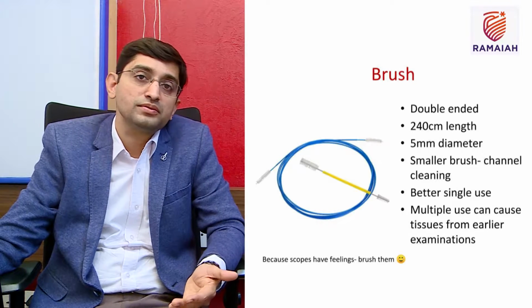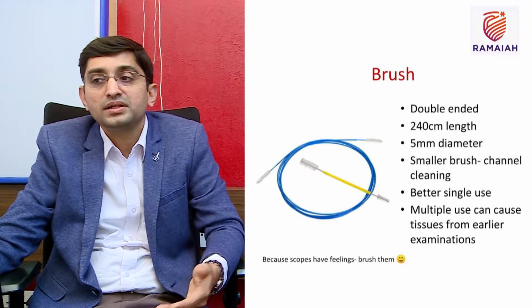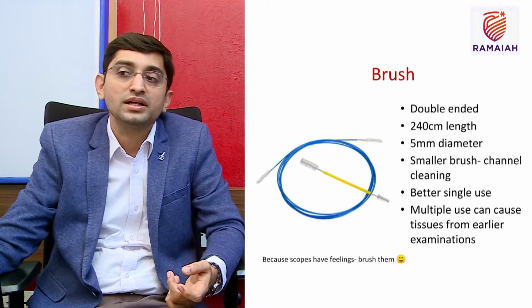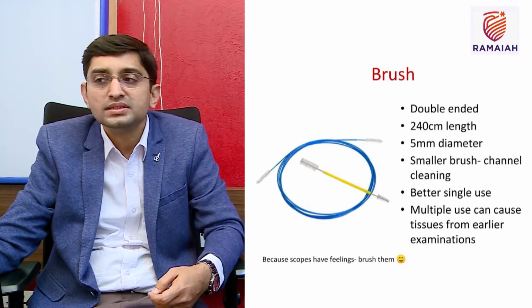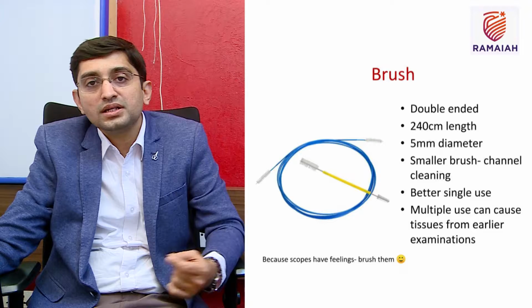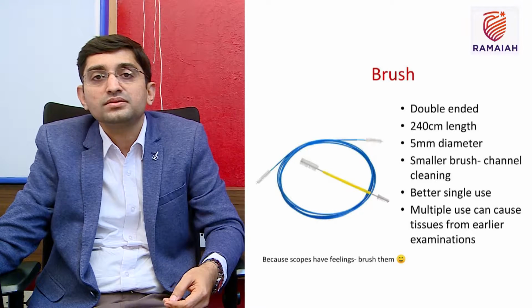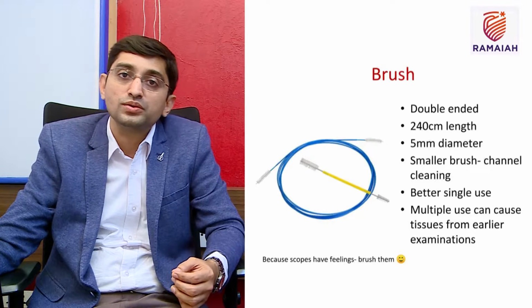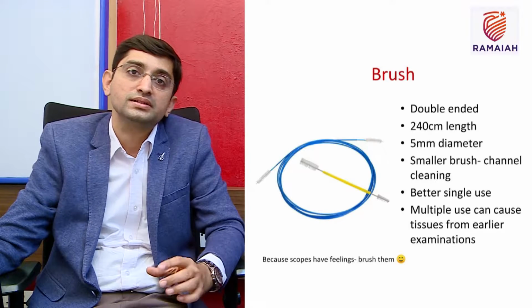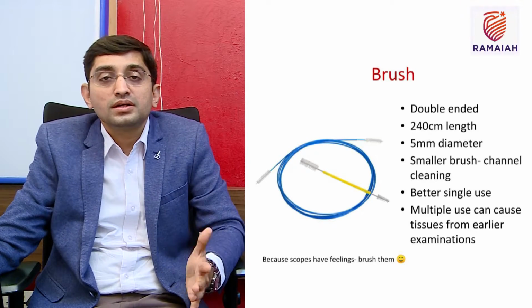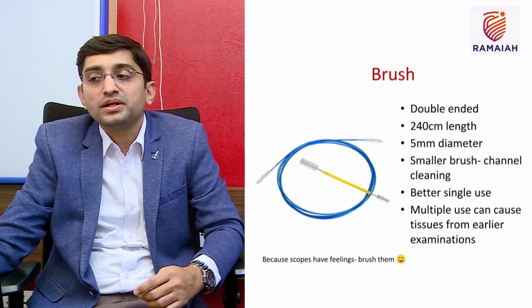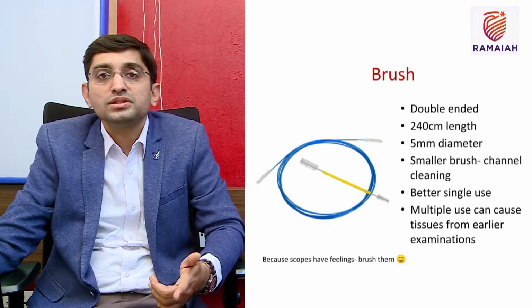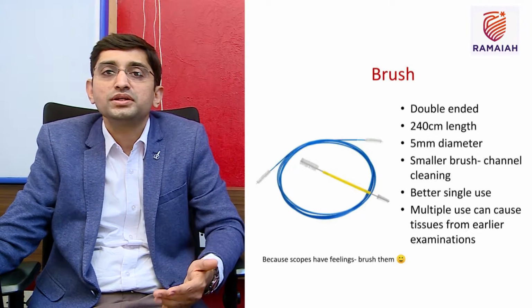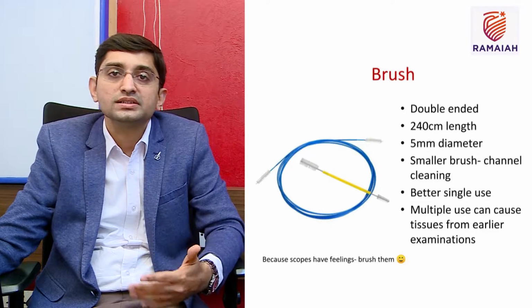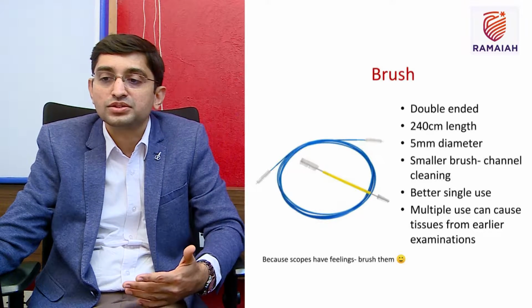You can use a scope cleaning brush, which comes in 2 different sizes. One is a longer tube, which is around 240 or 200 centimeter. The second one is a smaller tube, around 10 to 15 centimeter, with a brush at both ends. Whenever we use the longer one, we use it through the biopsy port as well as the channel port. We use a to and fro movement so that if any debris is stuck in the biopsy port, it will be removed completely. We should always use a brush a single time, but majority of the time we use it for 3 or 4 cases because these are costly instruments.